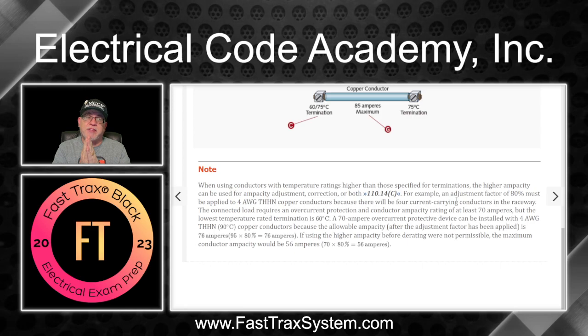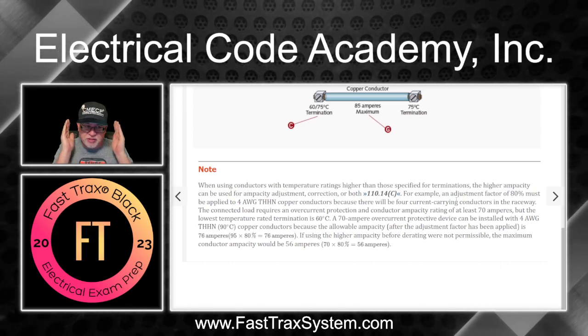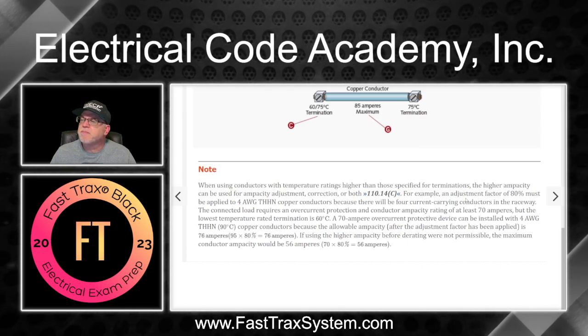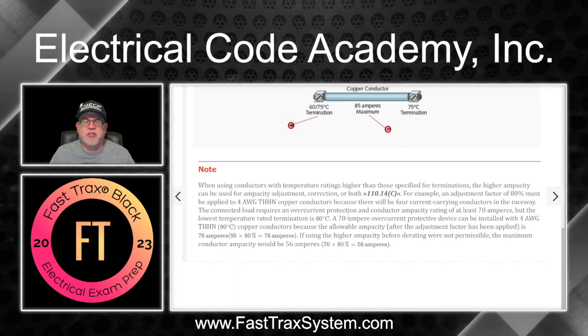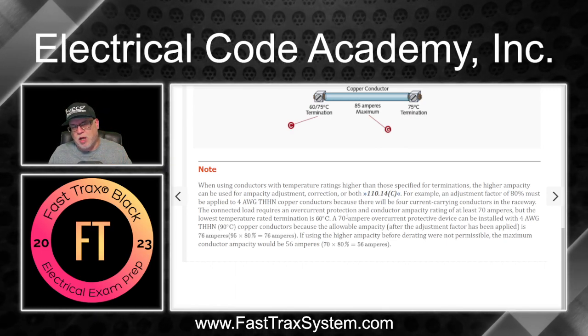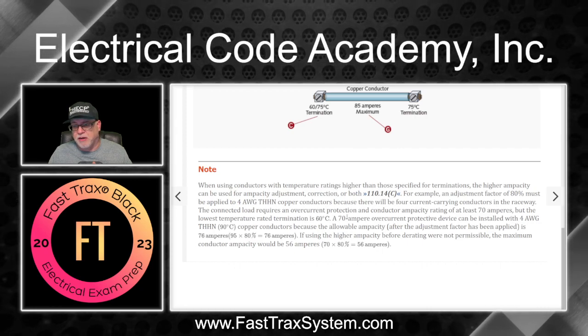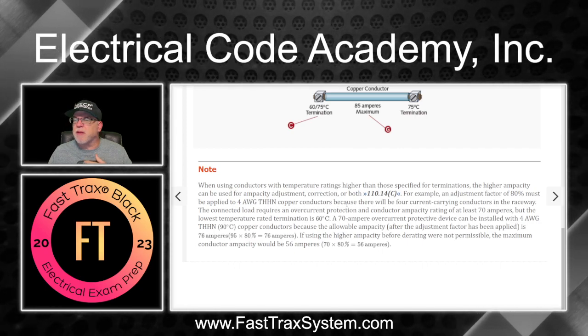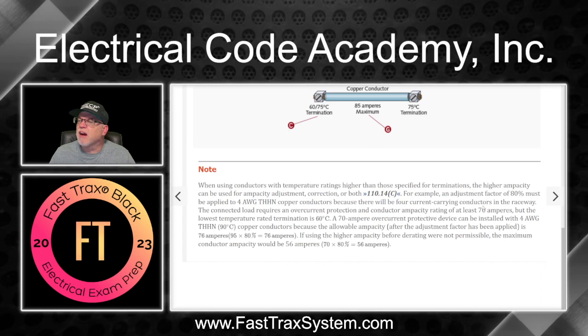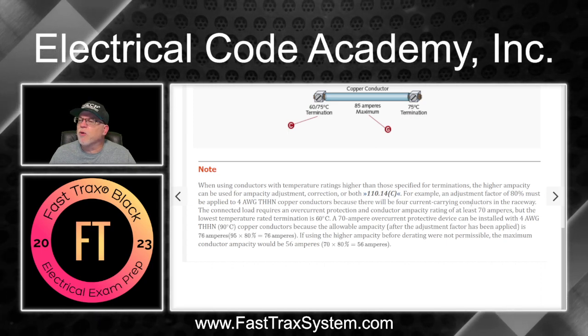Certainly not to take the place of Derating Demystified, but again, I'll just give you the example. If you have 4 current carrying conductors, if you go look at 310.15(C)(1), it'll tell you you're going to have a multiplier, and you're going to have to multiply that by 80%. All right? So we do that for 4 current carrying conductors.